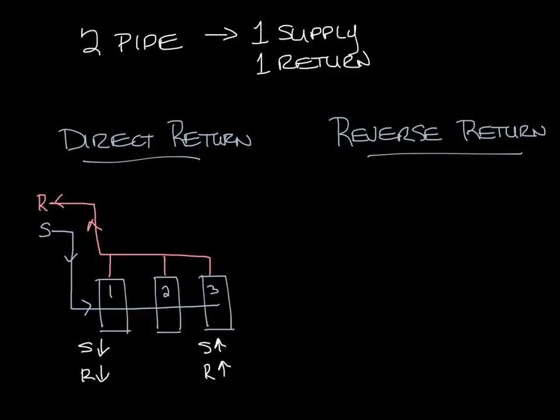In reverse return piping the losses from the supply through the unit and out the return are balanced through the three units. So let's draw our three units again and have our supply that looks the same as before coming in through the first unit to the second to the third. But your return looks like this.